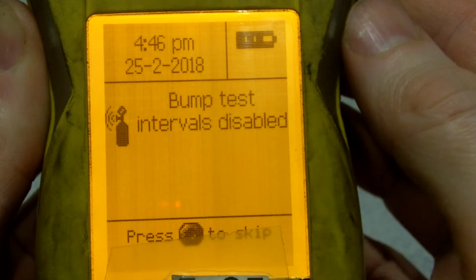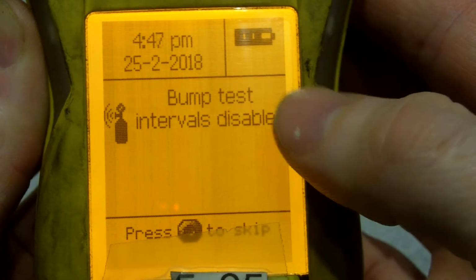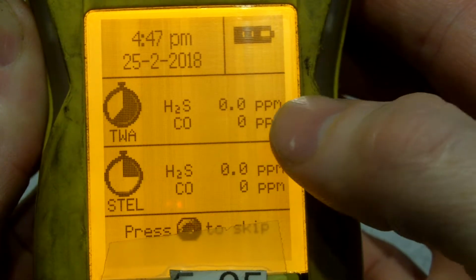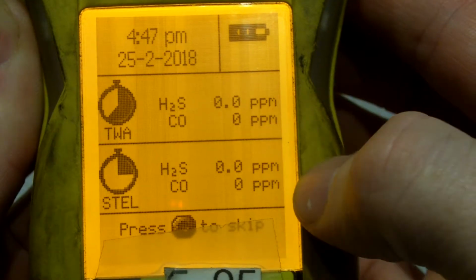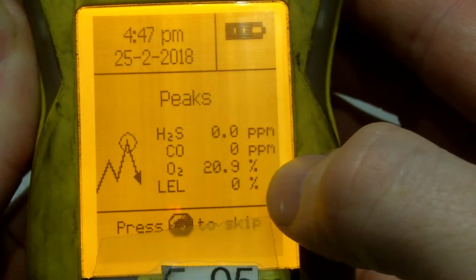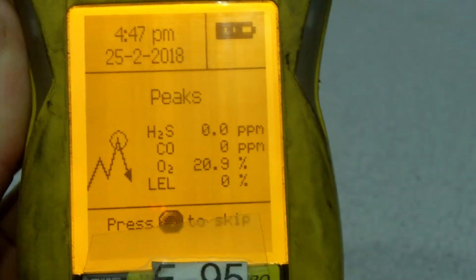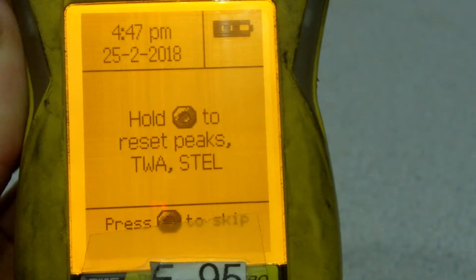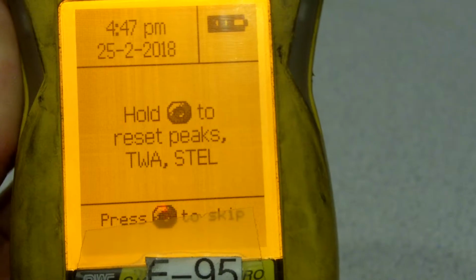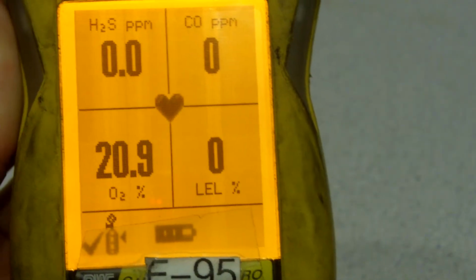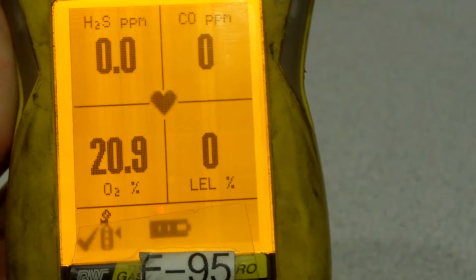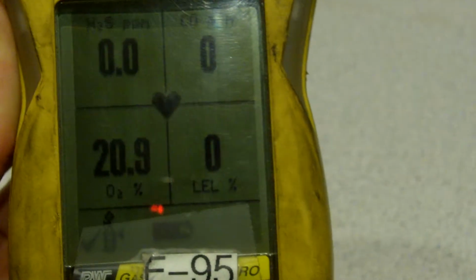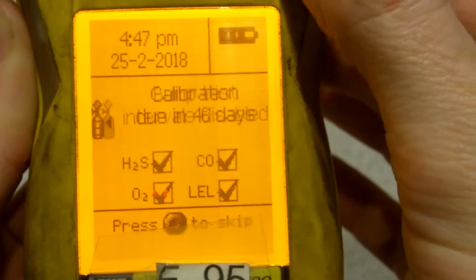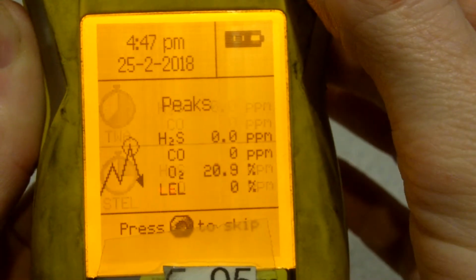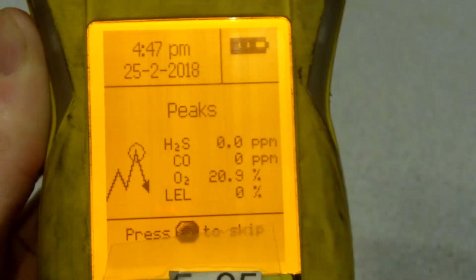It runs through a variety of displays, but there's one coming up here. These are my time-weighted averages. It says my 0 at that time. Here's my peaks. This is an important screen. So if you end up using this gas monitor and you hook it to a lanyard and you drop it down, say a sewer, and the alarm goes off, when you bring it up, it will come back to 0 atmosphere, and you won't be able to know which sensor went off unless you actually double-click, go through, and then get to your peaks, and it'll display what you had as the highest.